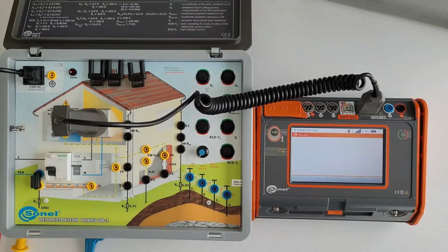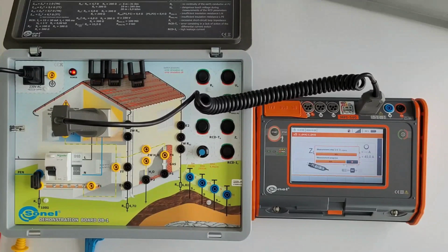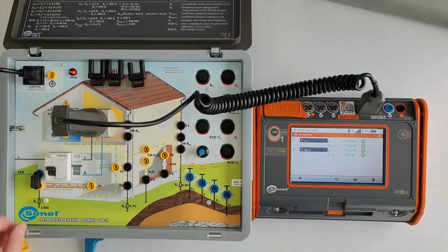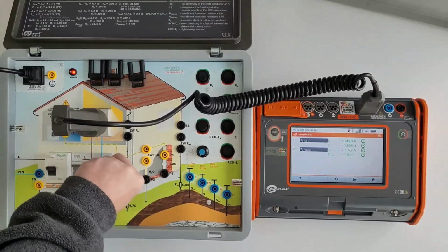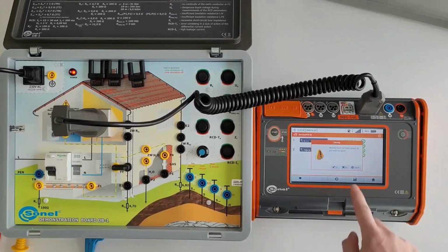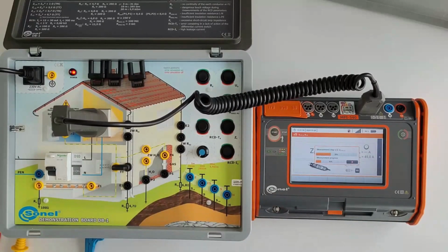Okay, now you can see we make the measurement of loop impedance in the TN system. First live-neutral, now live-protective. And as you see, the values are almost the same. The difference is very small. Now we do this on the TT system. So the difference is bigger.